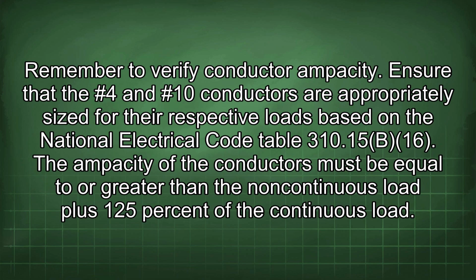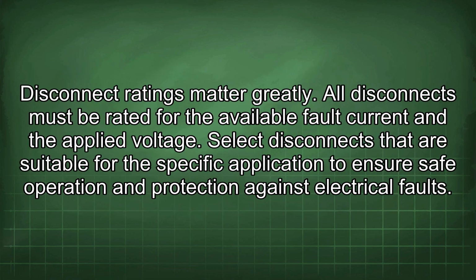Remember to verify conductor ampacity. Ensure that the #4 and #10 conductors are appropriately sized for their respective loads based on the National Electrical Code Table 310.15(B)(16). The ampacity of the conductors must be equal to or greater than the non-continuous load plus 125% of the continuous load. Disconnect ratings matter greatly. All disconnects must be rated for the available fault current and the applied voltage.